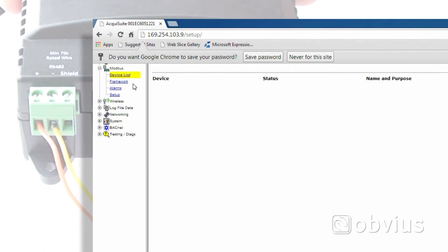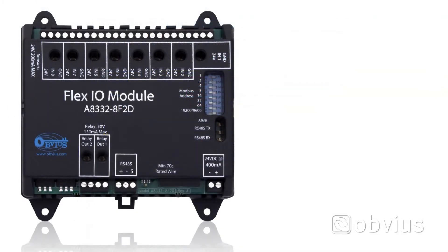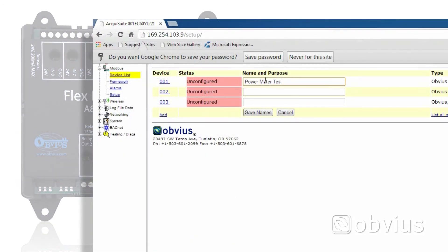The next step is to begin adding Modbus devices to the AcquiSuite. Click on the device list. The following screen will show devices that have been connected to the AcquiSuite. In this example, an Obvius FlexIO module has been added. For the AcquiSuite unit to begin logging data, you must name all connected devices. Click on the listed device and provide a unique name for the particular meter or sensor. You have now installed your AcquiSuite server and are logging data from your connected devices.